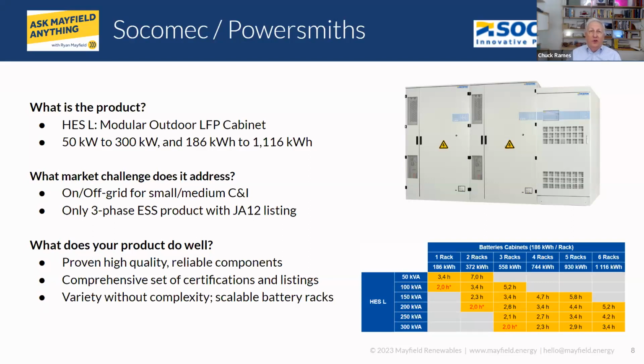Socomec manufactures the power converter, from the converter modules to the switches to the chassis. We build the whole thing, including the system-level controls and microgrid controls. The battery we integrate is lithium iron phosphate from CATL, the world's largest battery maker. This gives us both a modular converter and a modular battery. The table shows there are 22 UL certified configurations between 50 kilowatts and 300 kilowatts, and 186 kilowatt hours up to a little over a megawatt hour.